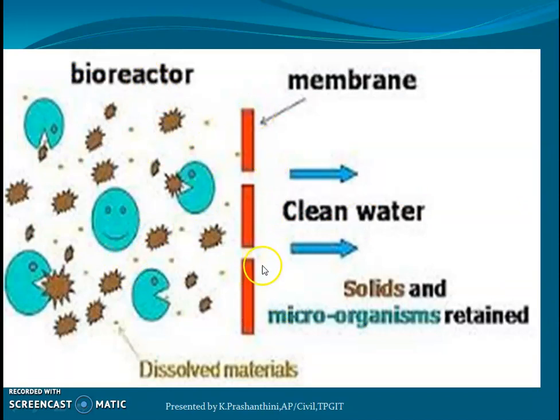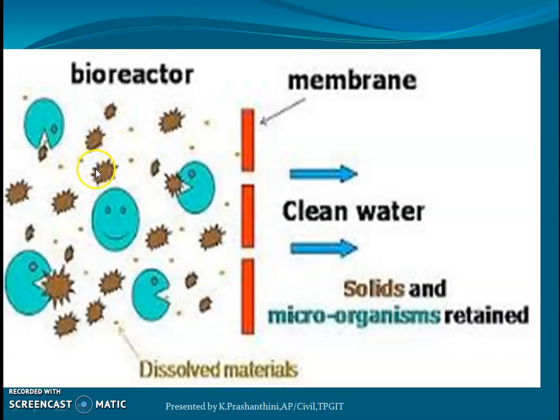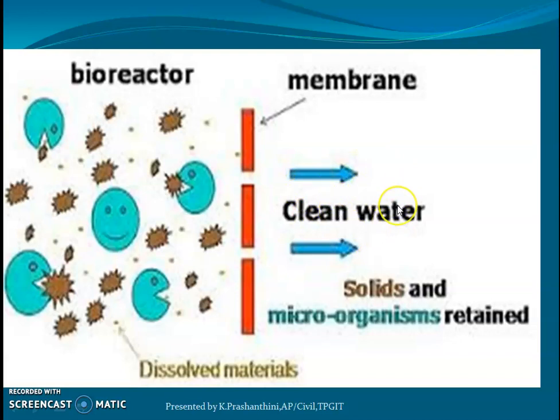The filtration mechanism shows the membrane represented by a red line, with pore sizes ranging from 0.035 micrometers to 0.4 micrometers, covering microfiltration to ultrafiltration. The bioreactor contains microorganisms and suspended solids of organic or inorganic nature. The membrane prevents these solids and microorganisms from passing through, allowing clean treated sewage to be obtained from the other side.